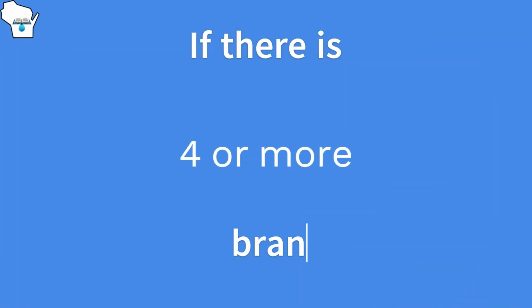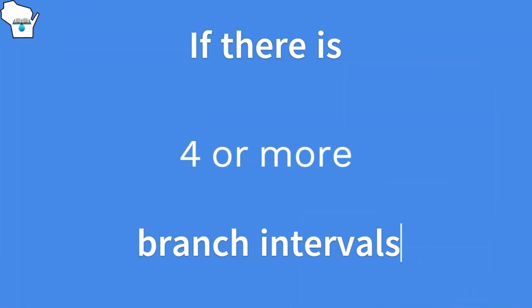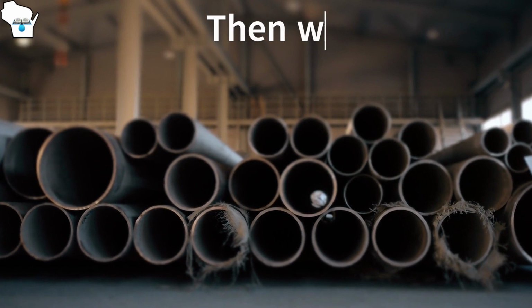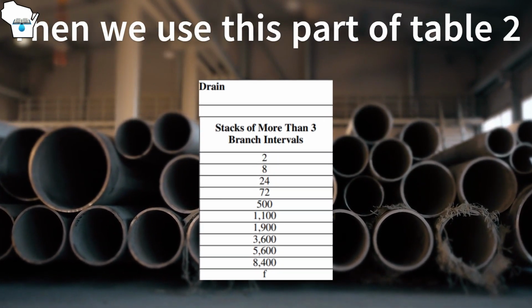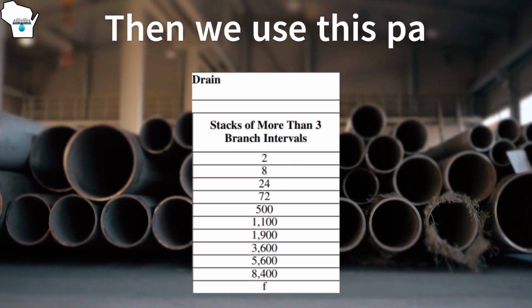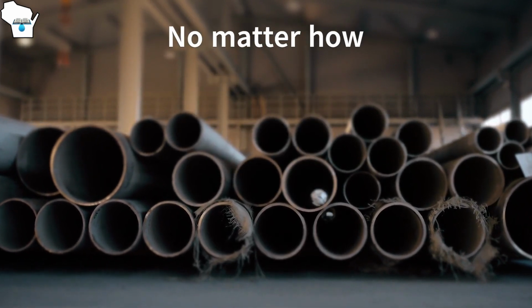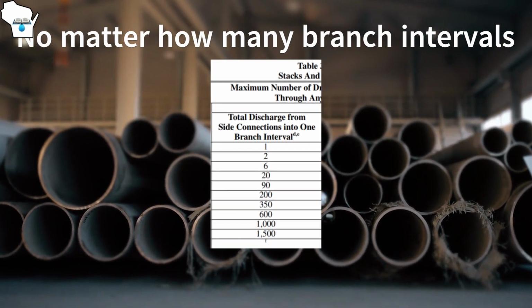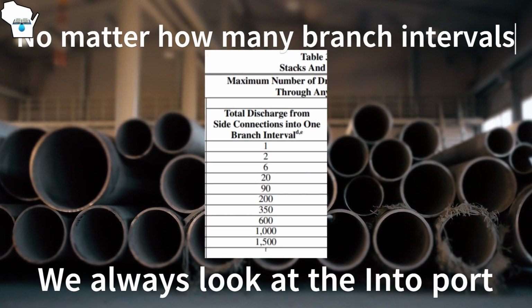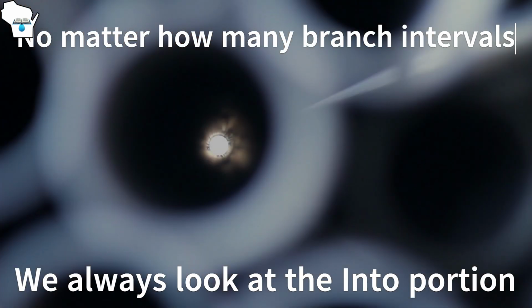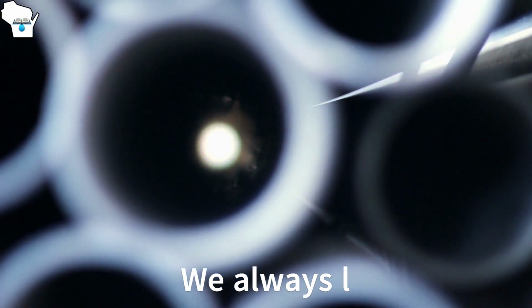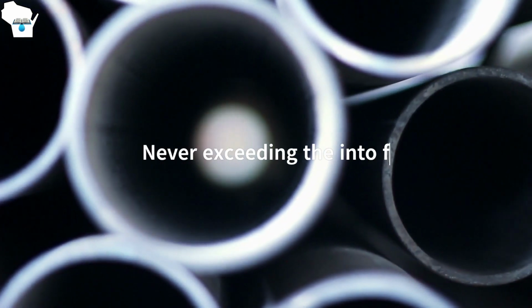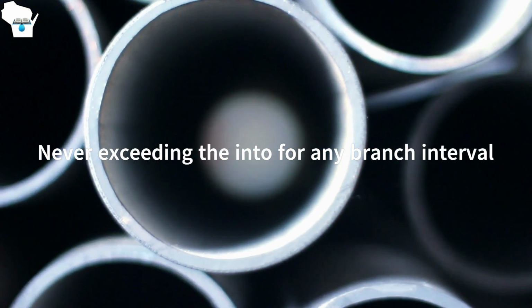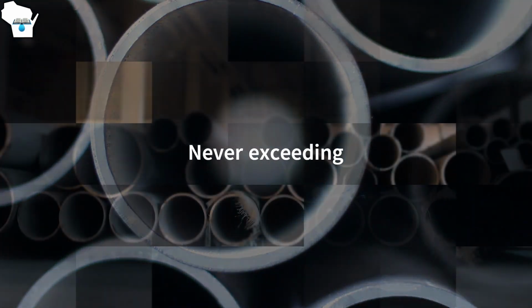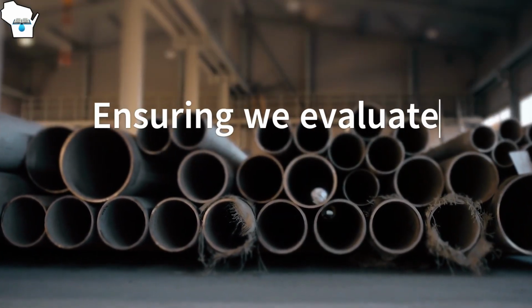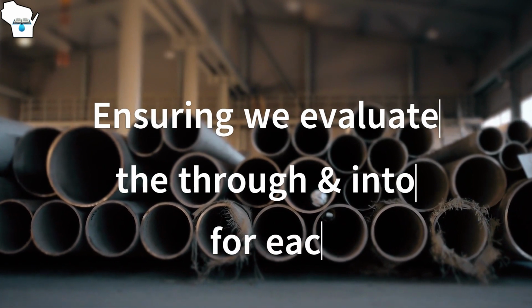If the amount of branch intervals on that stack is greater than 3, then we use this portion of Table 2 of 382.30. No matter how many branch intervals we have on a stack, we want to ensure we do not exceed the allowable amount of any one branch interval. When sizing stacks properly, we have to ensure that we're incorporating the pipe size for the DFUs of through as well as into every single branch interval.